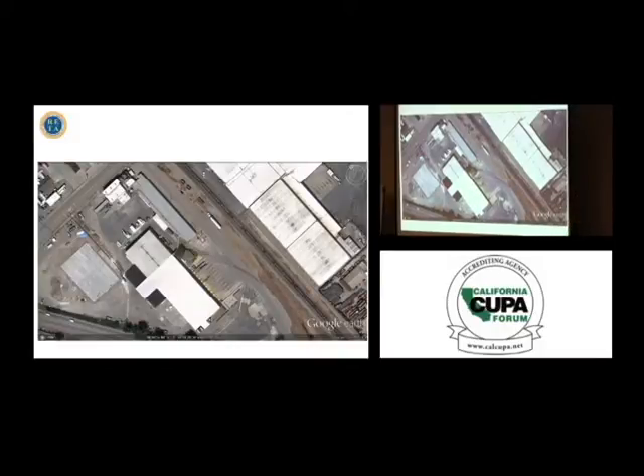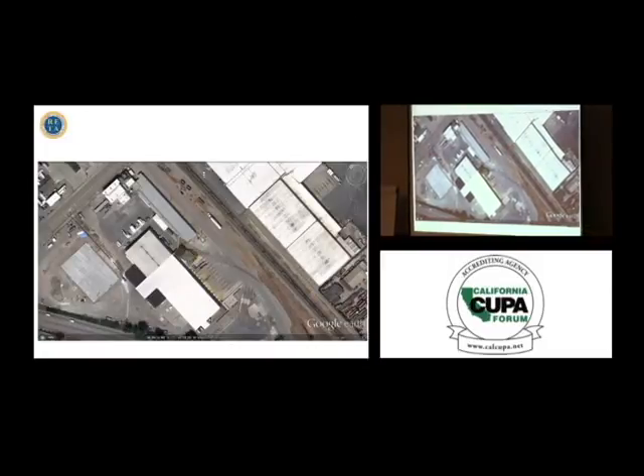There are evaporators that move a lot of air, about 30,000 cubic feet per minute per fan, to bring a lot of cold air. I shouldn't say fresh because that implies it's coming from the outside, but we bring air across the product to rapidly bring the temperature down. So our job here is to maintain the temperature in that room, because if it's too cold, we freeze the berry, and that doesn't work for us. And if it's not cold enough, it doesn't get cold in the time that it takes, and we have quality issues.